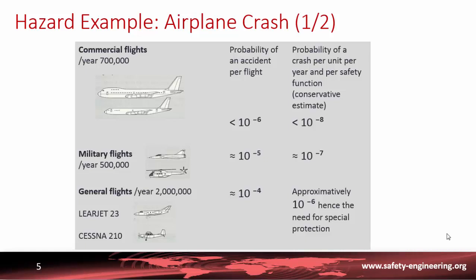For military flights, the number of flights is a little lower, but the probability of accident per flight is about ten times more than for commercial flights. Therefore, the probability of a military aircraft crash is on the order of 10^-7. In general, military flight crashes are not considered unless a nuclear plant is sited not very far from a military airfield. In some countries and some areas, nuclear plants are protected against military flight crashes.